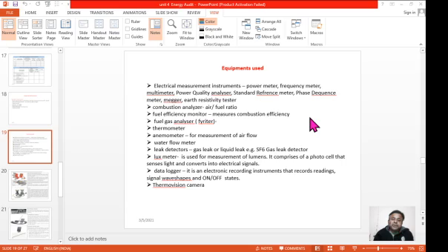So after taking review of joints, we can come to know which joint is having hotspot, and accordingly that hotspot is attended. Because of thermovision camera, a lot of interruptions have been avoided, because well in advance we come to know that this hotspot is going to take the shape of red hot, which is very dangerous. It may give rise to fire hazards or bus faults or flashovers, which is very dangerous.